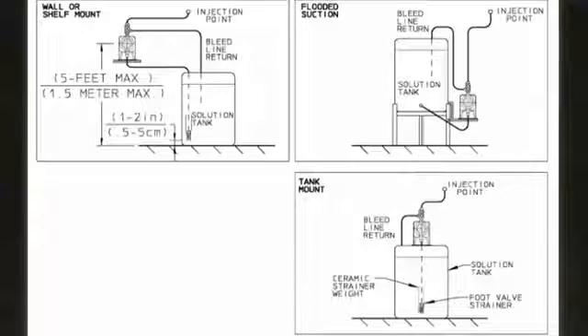A flooded suction or tank mount installation is preferred. For optimum performance, the distance from the pump head and the lowest possible fluid level in the supply tank must not exceed five feet. The injection point must be higher than the top of the solution supply tank to prohibit gravity feeding. Installation of an anti-siphon valve will prevent this from occurring.